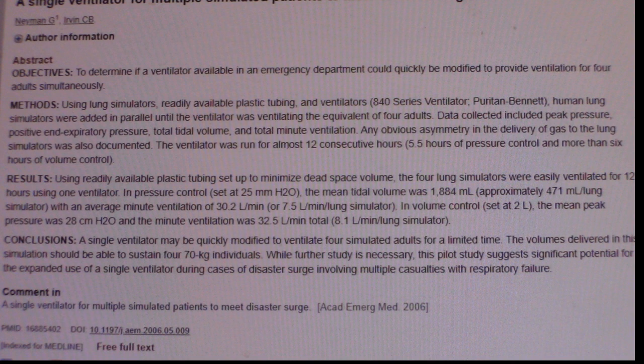People were added to the ventilator in parallel. So you just take the tubes out and parallel the tubes to each patient, until the ventilator was ventilating the equivalent of 4 adults. Data was collected including peak pressure, positive end expiratory pressure, total tidal volume, and total minute ventilation. So the medical people will know what that means. I got a little bit of an idea, but medical people will know what that means. Any obvious asymmetry in the delivery of gas to the lung simulator was also documented.